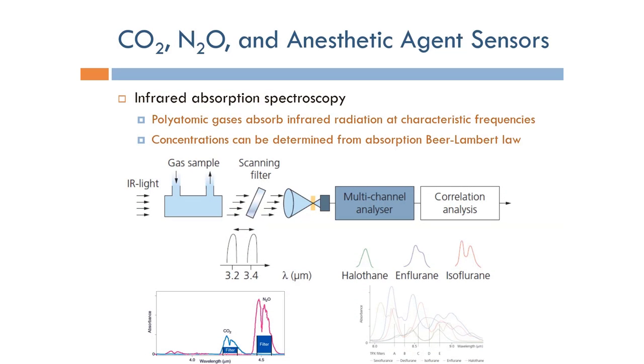The way we measure all gases involved with an anesthesia machine, including carbon dioxide, nitrous oxide, and anesthetic agents, we use something called infrared absorption spectroscopy. Infrared absorption spectroscopy relies on the fact that polyatomic gases absorb infrared radiation at characteristic frequencies.